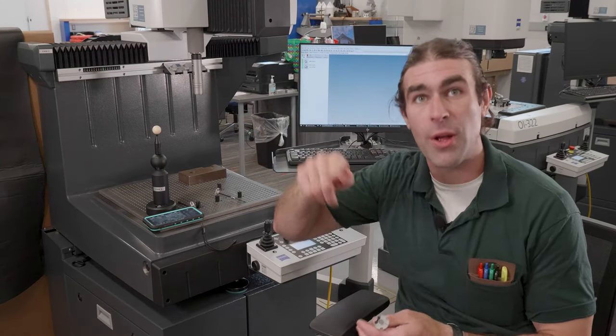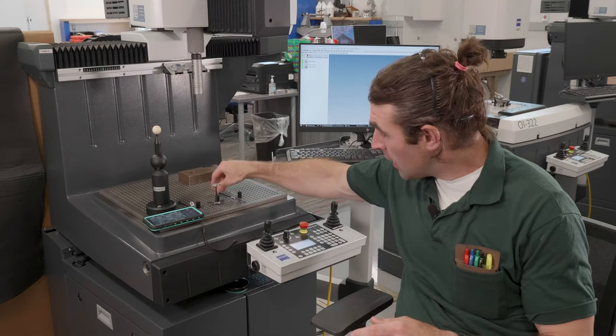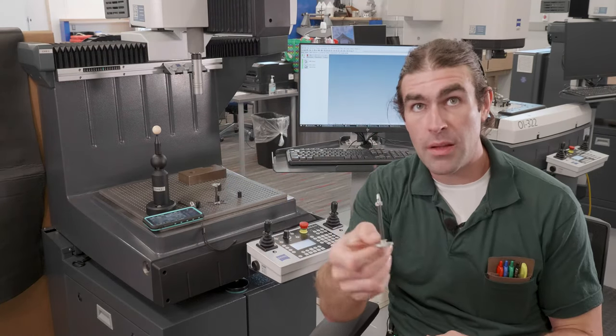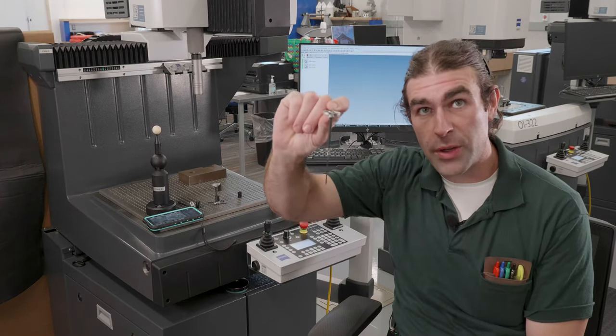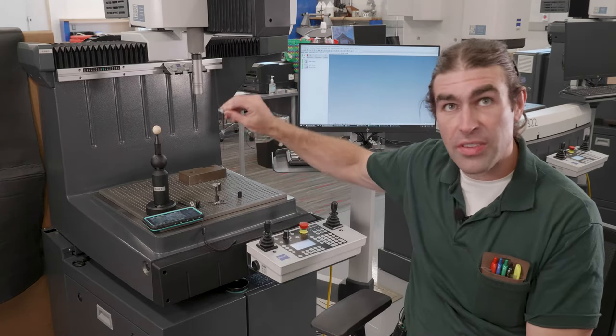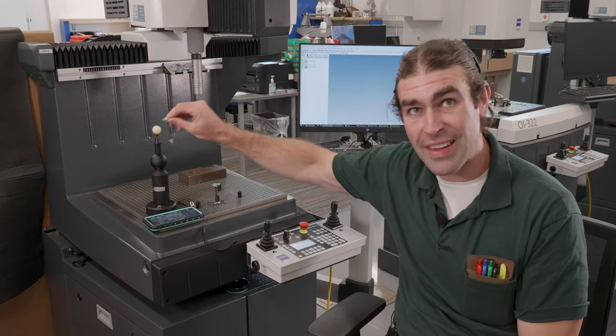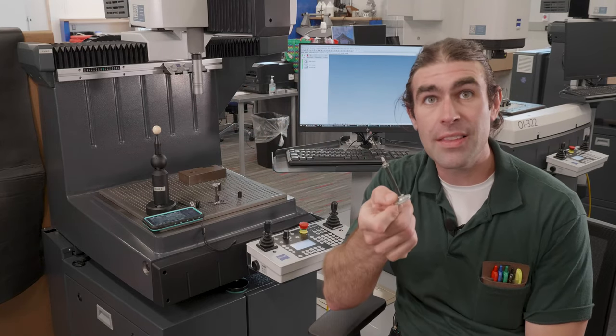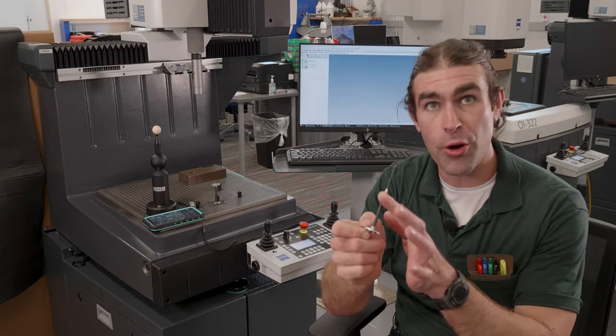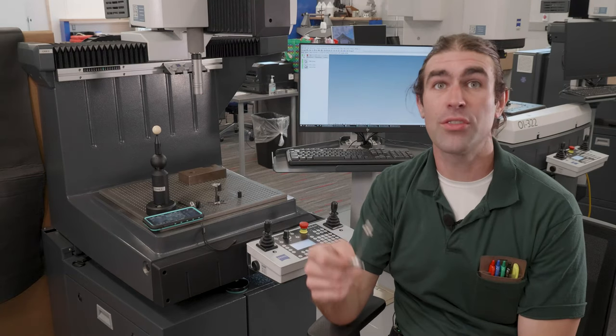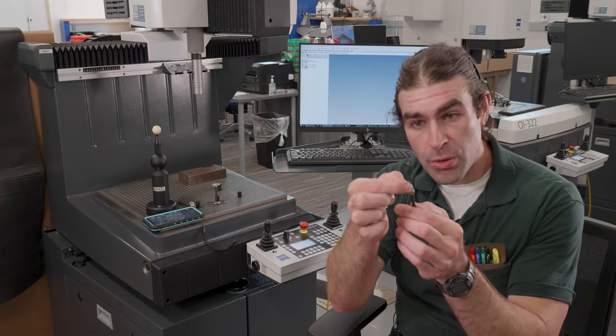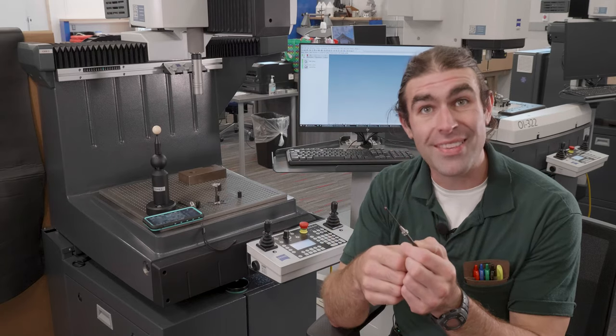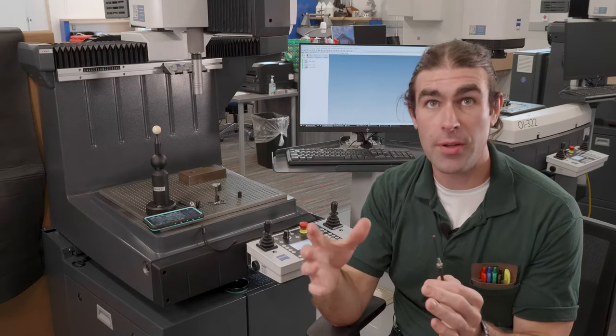So you have like a horizontal hole you want to measure. A more typical probe is just straight down. So this would come in if you're checking the top of a part or even the size of a shallow part. Now each individual little tip here is called a stylus and they all have to be qualified separately.